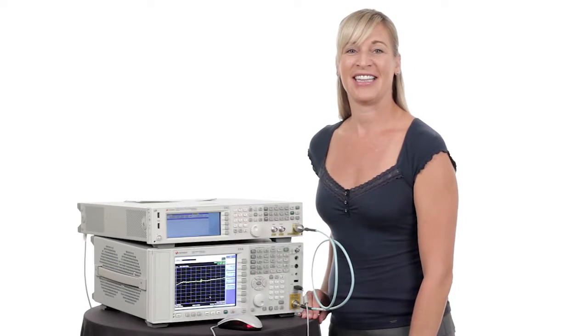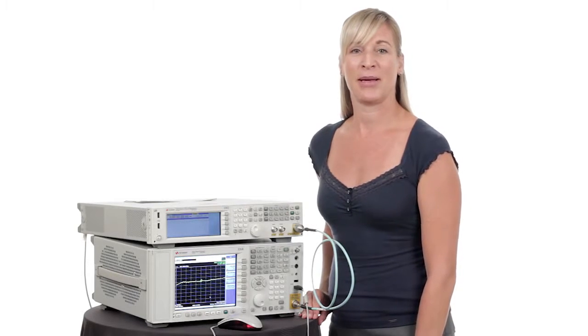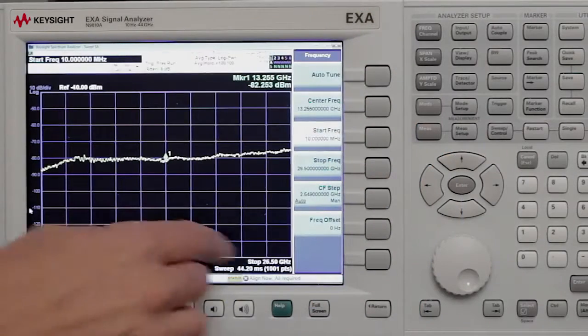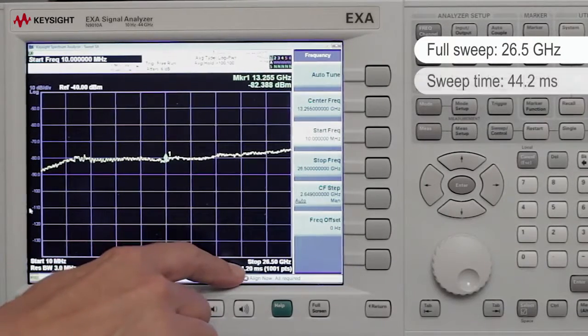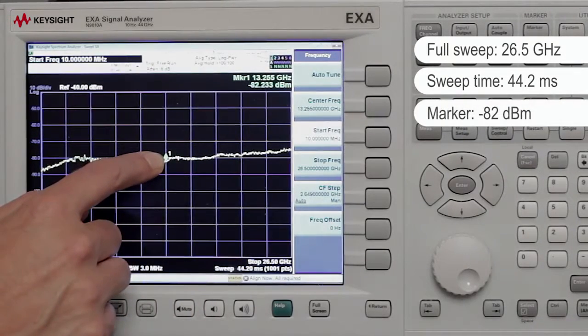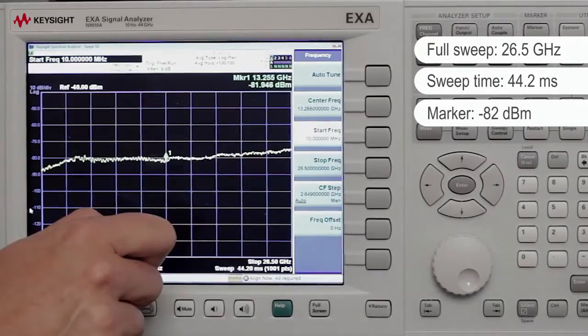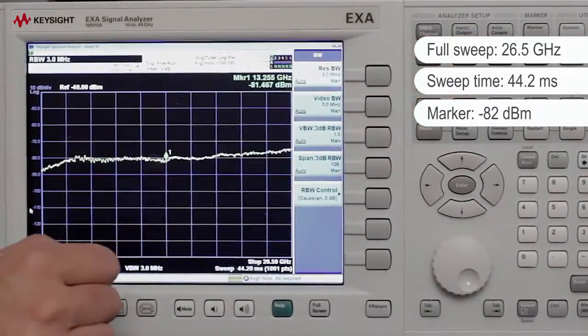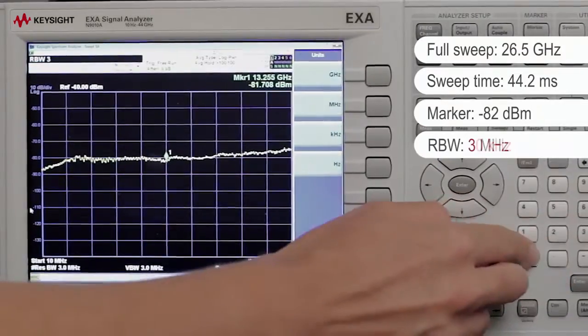Now let's take a look at the EXA's new fast sweep capability. When you're looking for spurs you need to be able to sweep quickly as well as have excellent sensitivity. We're doing a full sweep up to 26.5 gigahertz and our sweep time is 44.2 milliseconds. Notice the reading at marker one: minus 82 dBm. If we're looking for spurs lower than minus 82 dBm, we can lower the noise floor by changing our resolution bandwidth — right now we're at 3 megahertz, so I'll change it down to 30 kilohertz.